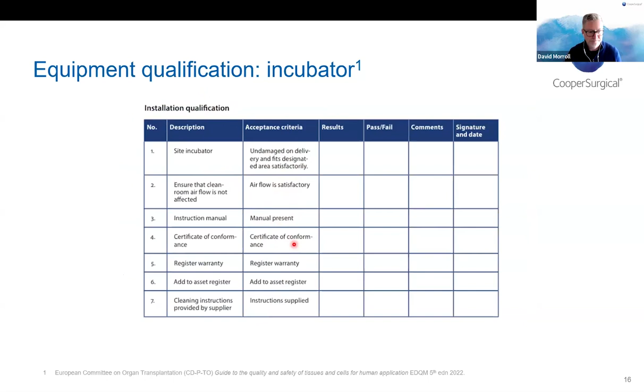It is around testing the functions of the incubator. Do the switches and the buttons do what they're supposed to do? Do they work? If it's got shelves, are they fitted correctly? Have you got an SOP for using that piece of equipment? Have you got records of it being appropriately cleaned and swabbed? And then, of course, the bits that we tend to focus on, which is setting temperature and CO2 levels. So again, you've got to understand what the target values are, and then test that they are being met.